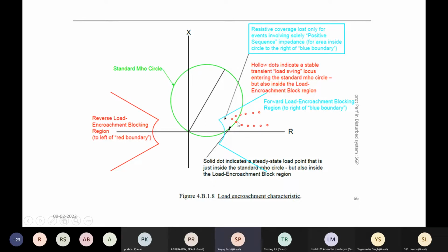As a mitigation of this, there is now a feature which has a load encroachment blinder characteristic. So this blue zone, you can see, is the load encroachment blinder characteristic, and as the load encroaches into the impedance circle of the zone 3, still the tripping is prevented because of this load encroachment characteristic. So in this zone, the tripping is prevented. Now you can see this zone is very close to the R axis. That means it is purely seeing only the loading phenomena, high overload phenomena, and is not susceptible to the fault phenomena.